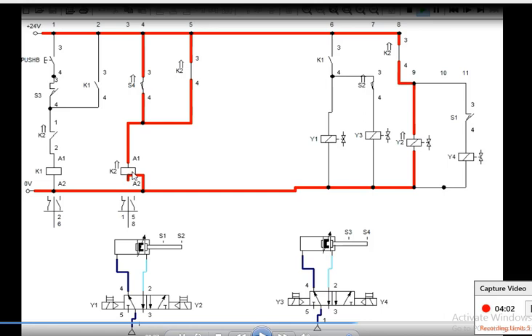The S4 contact is now closed because of the piston position, and current goes to the K2 coil. The K2 coil is energized and closes the normally-open K2 contact through magnetic action. It also opens the normally-closed K2 contact. So when K2 gets energized, it opens the normally-closed contact and closes the normally-open contact.